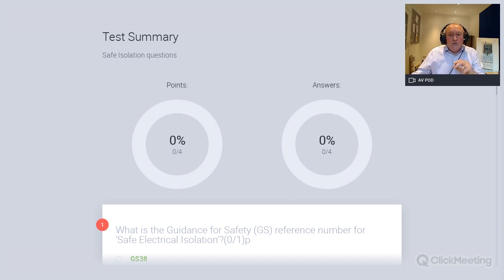And finally, which isn't a GS38 standard requirement? It's the 10 millimeter exposed tip. If you remember, when I made a point of showing you these, I said it should be 2 millimeters. Obviously 10 millimeters is a centimeter, that's quite an exposed tip. The more tip you've got, the more chance of touching it somehow, or touching the tip against a piece of earth metal and starting a short circuit. So it's actually 2 millimeters.